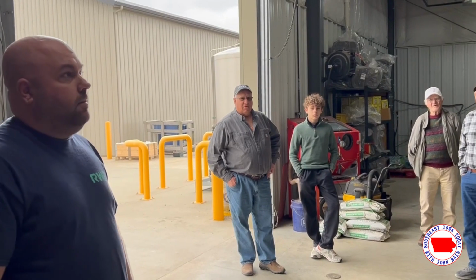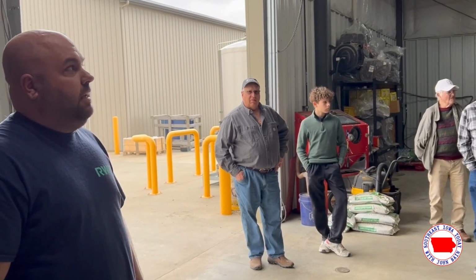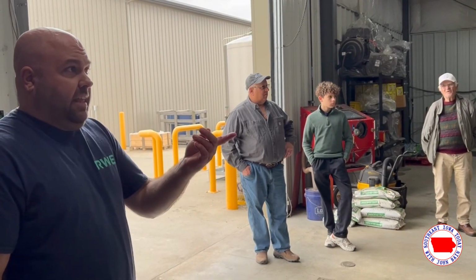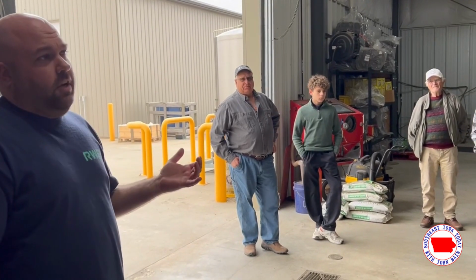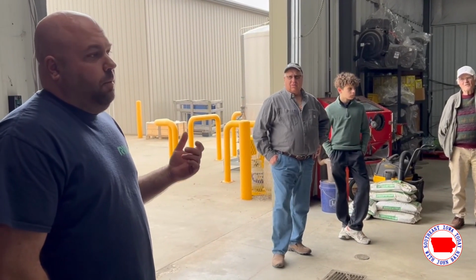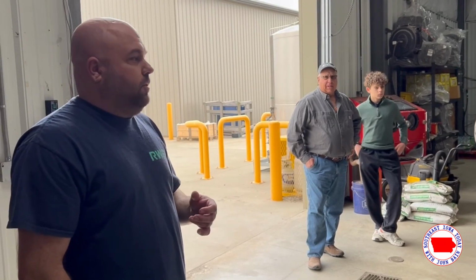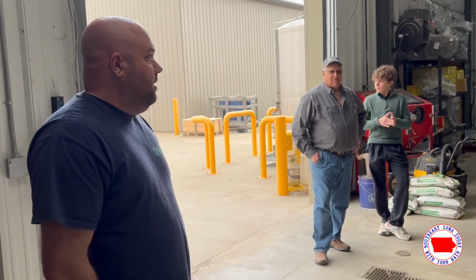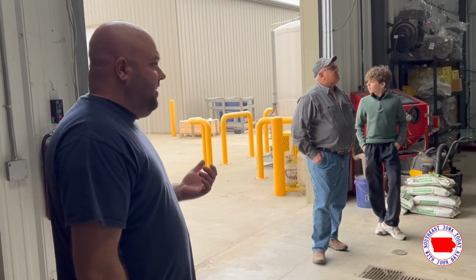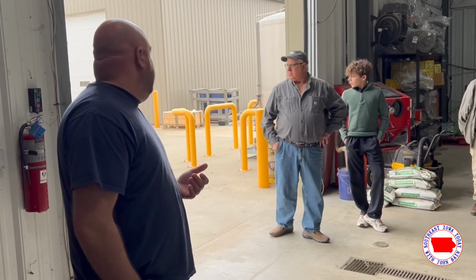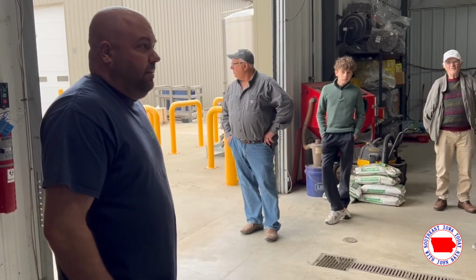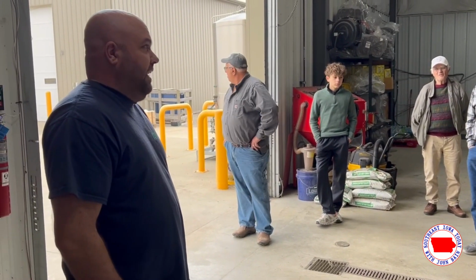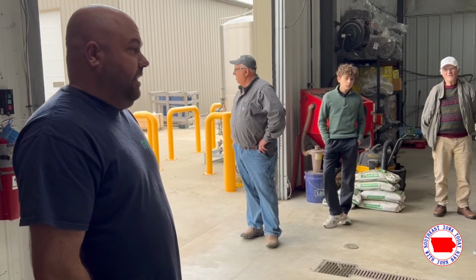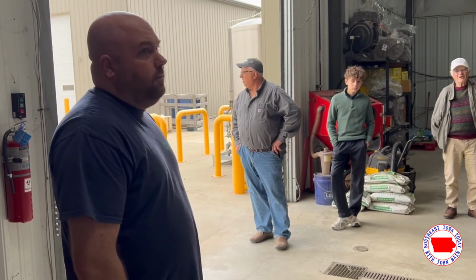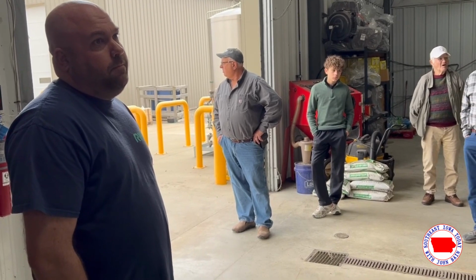These still have the original oil from the factory as far as I know. We change out filters regularly and pull oil samples regularly to send off for oil analysis. We don't want to change this stuff out more than we have to—it's a waste of money, a waste of time, not efficient. So it's here if we need it, but unless the oil analysis comes back bad, it's staying in there. It's just standard 80W90 gear lube.